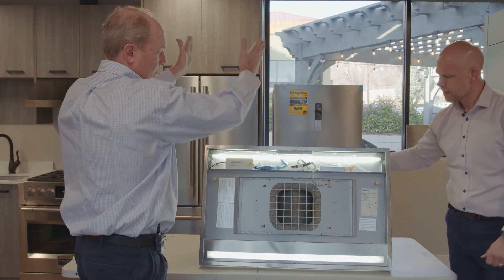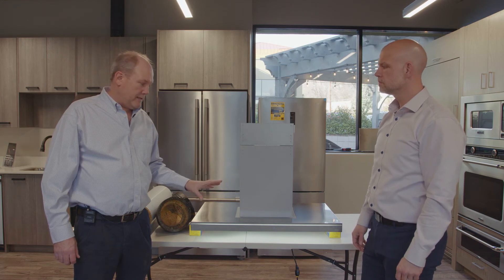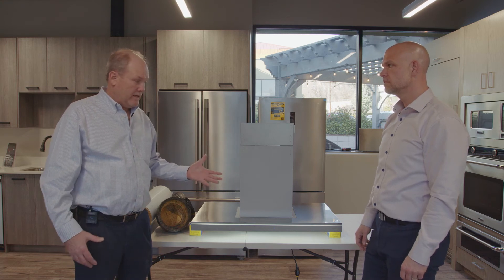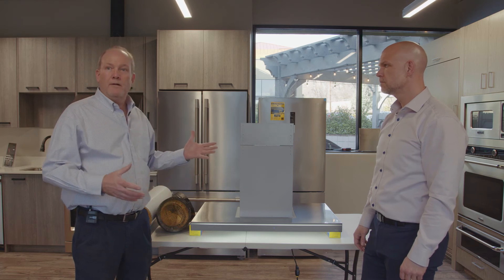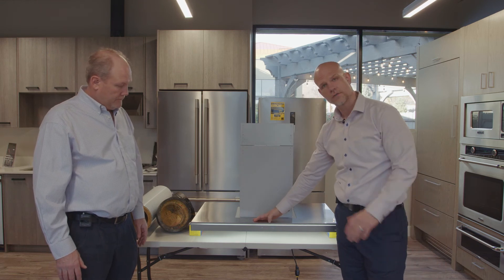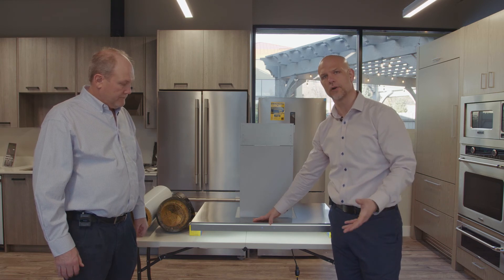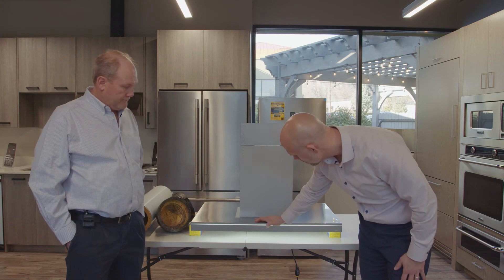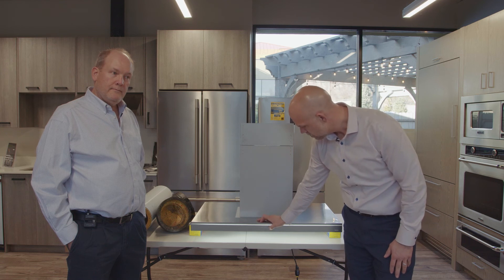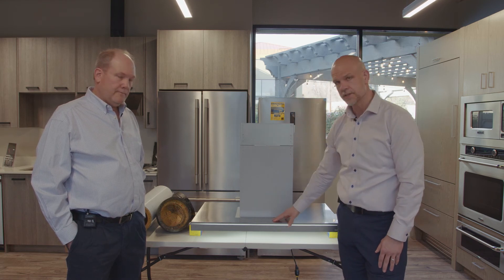There's a diverter in there to divert the air up and through the chimney. This is our test kitchen for the noise level on the NRS systems. We've taken all the filters out because we had to uninstall the hood, but we just want to give you an idea without any of the stack or elbow — just the noise level on this hood. That's speed one: quite low CFM but gets some air movement. Speed two. Speed three. And speed four — on this particular hood that's its maximum output at 500 CFM.